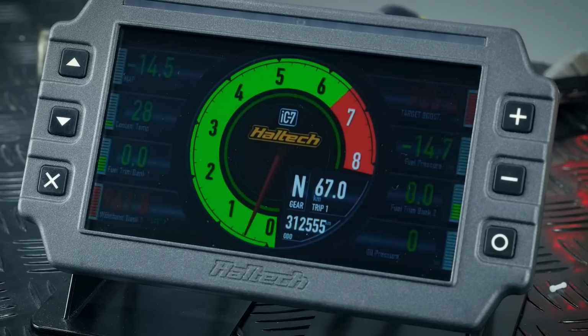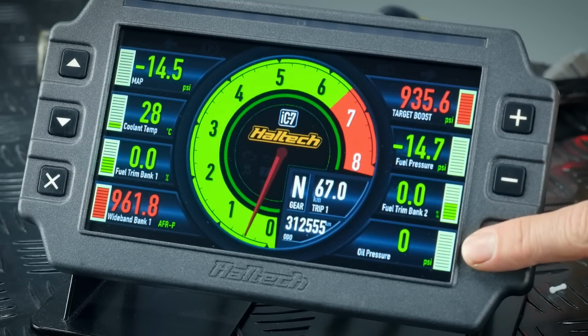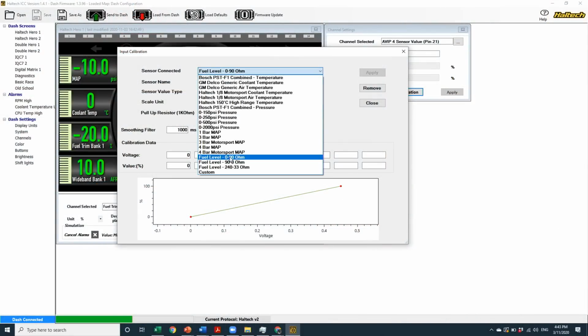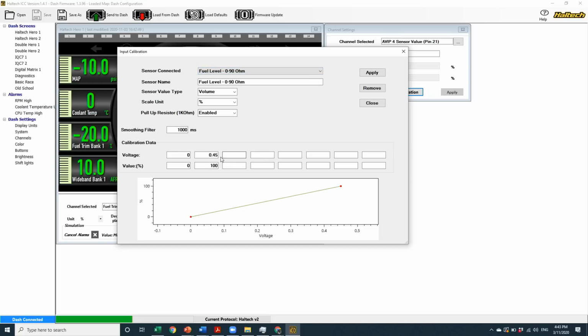Now it's worth taking the time to mention, you can use this AVI functionality to wire in your fuel level input directly to the dash. The process is exactly the same as what I just did here with the pressure sensor, with the difference being I'll select the input calibration to be fuel level, then either 0 to 90 ohms, 90 to 0, depending on which way the sensor goes, or the less common but still out there sensor, which goes from 240 ohms down to 33 ohms. So there's a rough calibration pre-configured in the software here, but it would be worth taking the time to check the actual voltage reading of your fuel level sender when the tank is full and when it's empty to get a more precise calibration of fuel level. No one wants to get stuck on the side of the road without fuel.